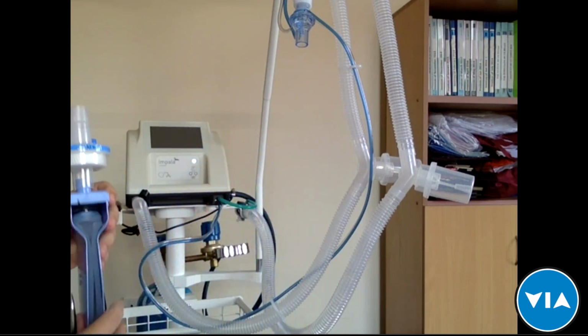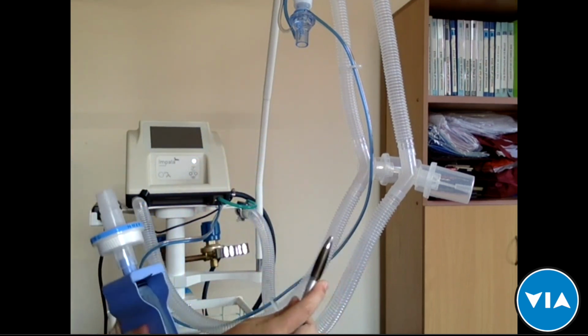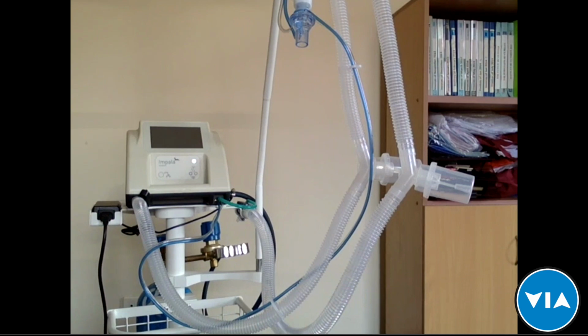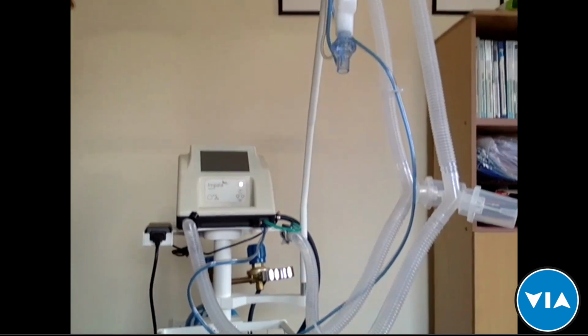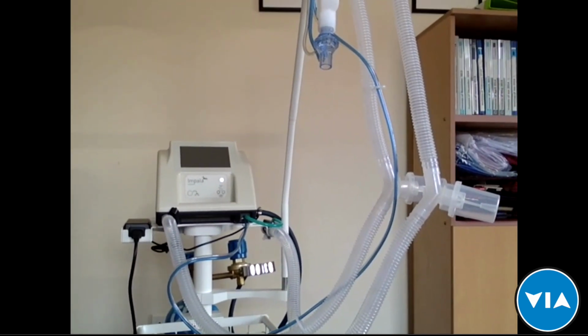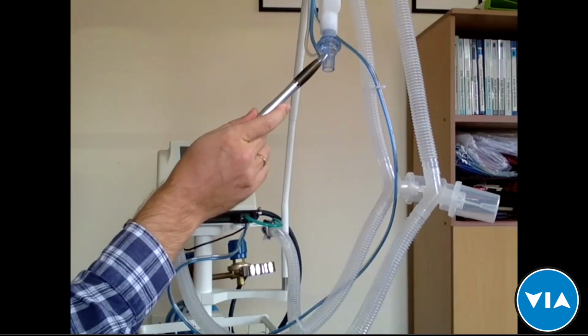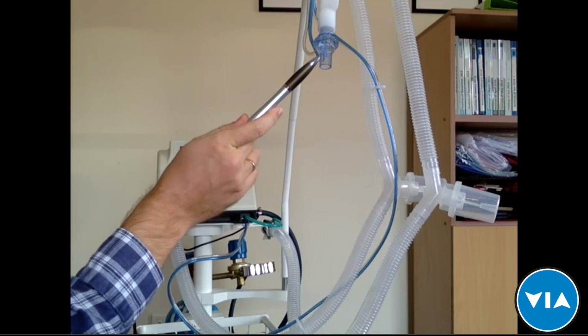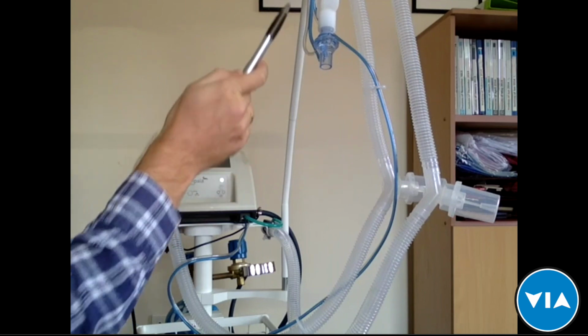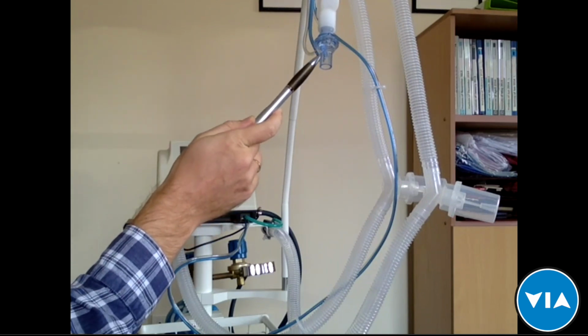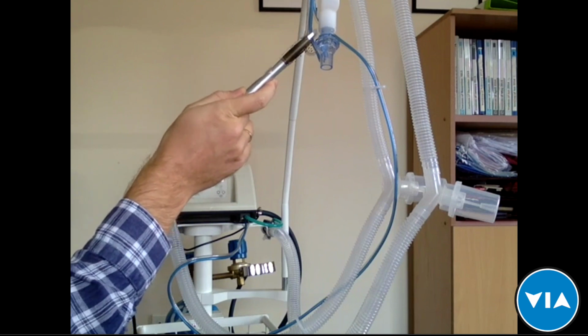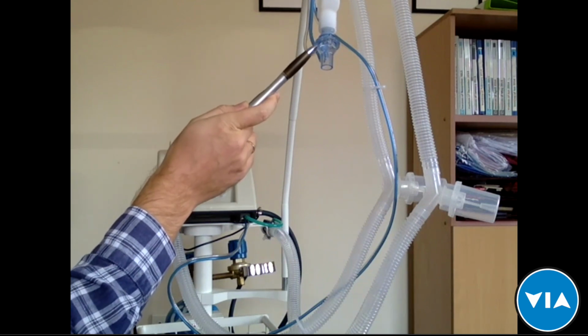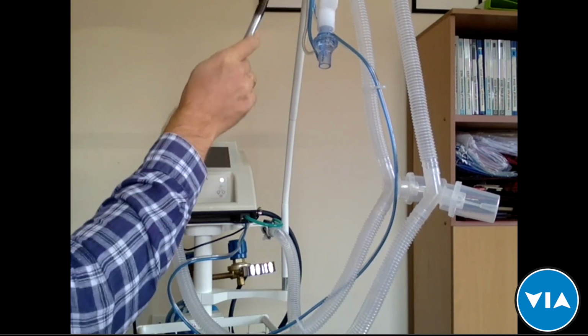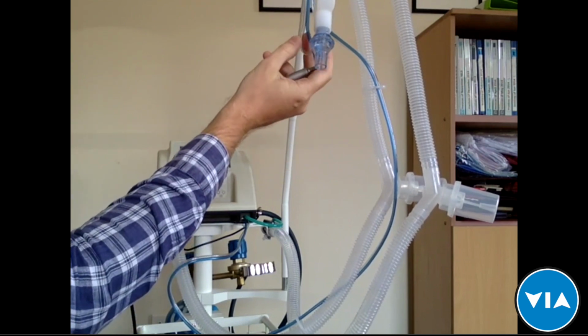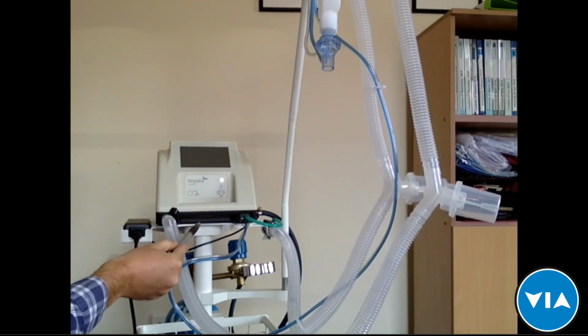the presentation. A very important feature of this patient circuit is the fact that it has two elements that determine the choices for the doctors for the setup. The flow meter. This element is external, and in this case it's reusable, but there are also disposable ones. So the flow is measured here and transferred through those two tubes to the unit for measurement.